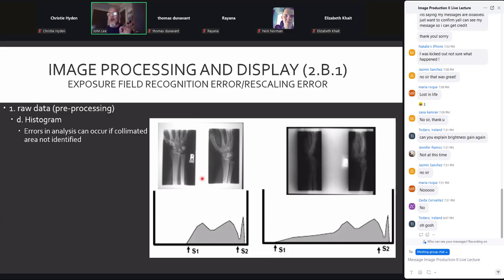But CR did have this quirk where if it didn't recognize four collimated borders around an area of high concentration of data, it would assume that all of the information was part of the image and consequently part of the anatomy. And so when the lookup table would go to make an adjustment, it would lengthen the histogram. So the values of interest and the number of them grew. And so we would get what was known as a histogram analysis or a rescaling error. This is where the image just looks dark.